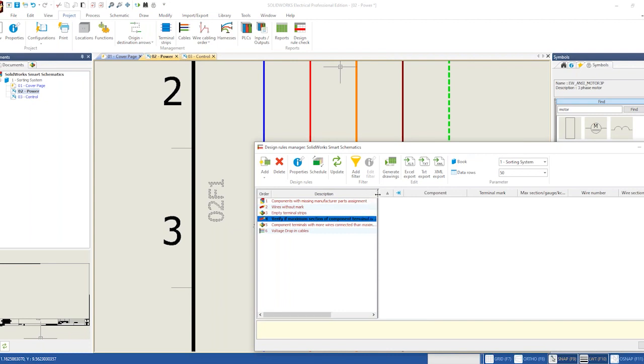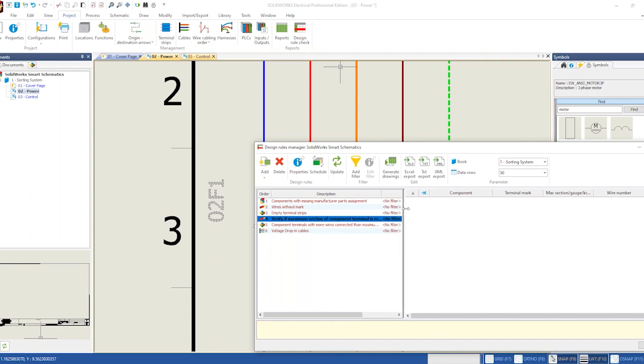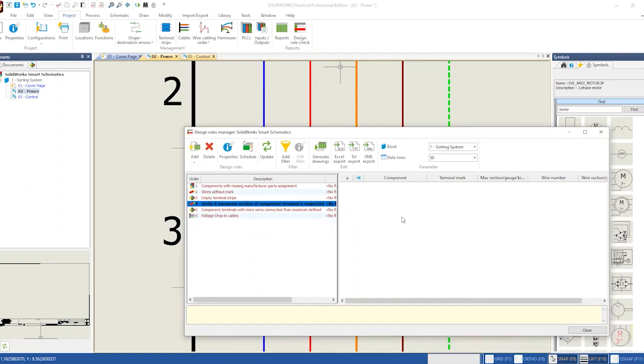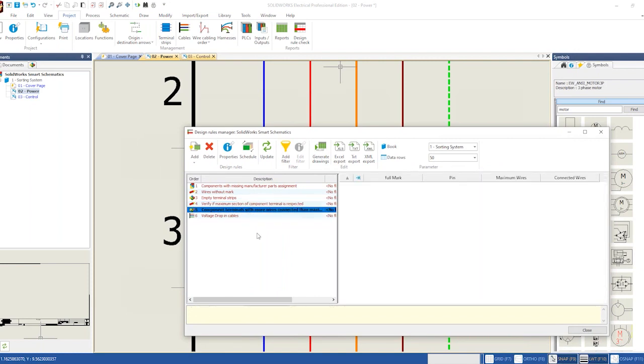Also here's one that says verify maximum section of component terminal is respected. So what that means basically is verify that according to the manufacturer spec, I don't have a wire that's too big for that component. And sometimes manufacturers will specify that you can only have so many wires per connection point on that device, so you can check to make sure that's also adhered to.